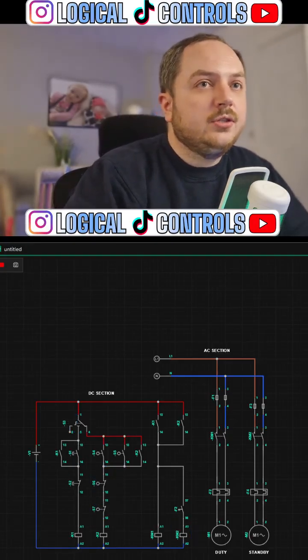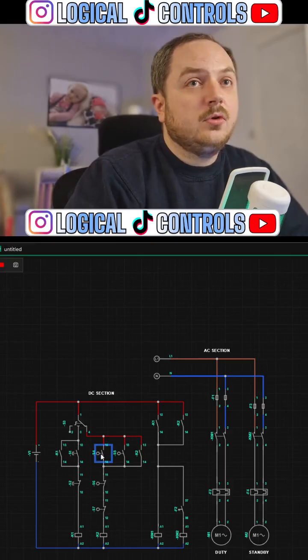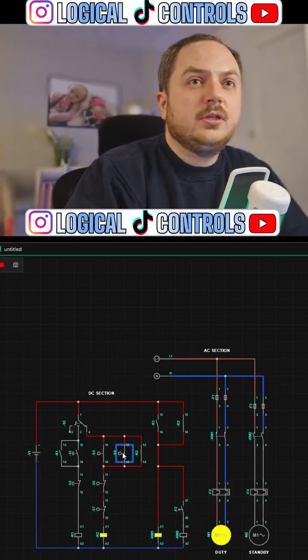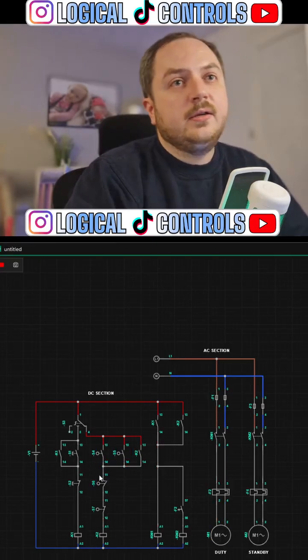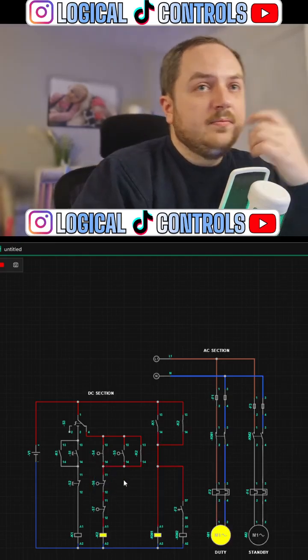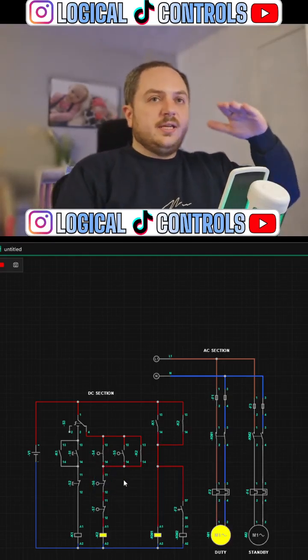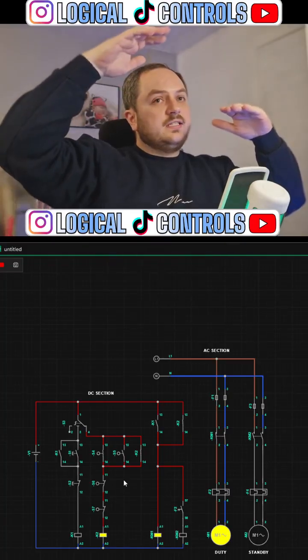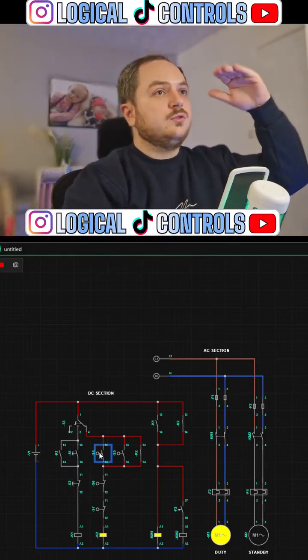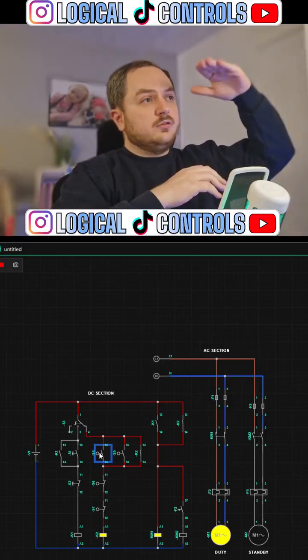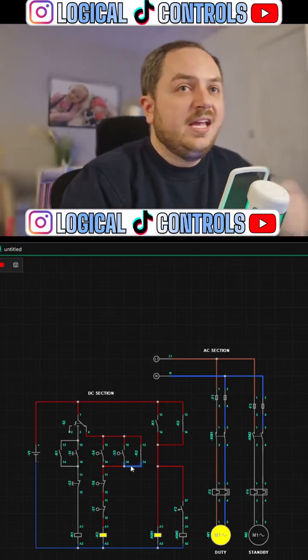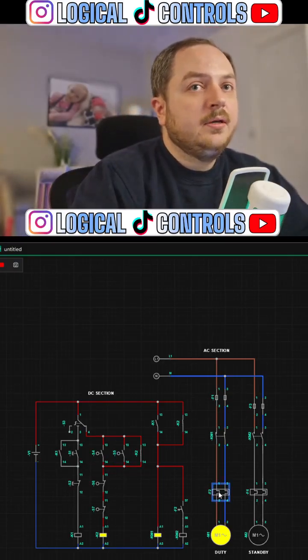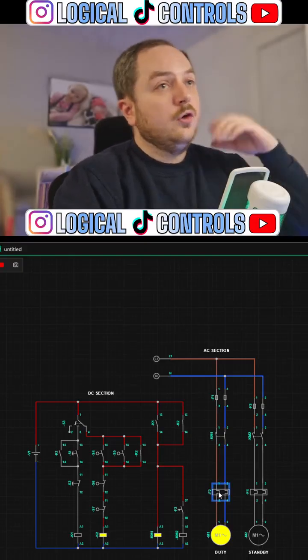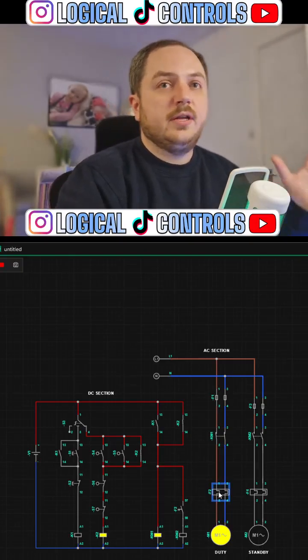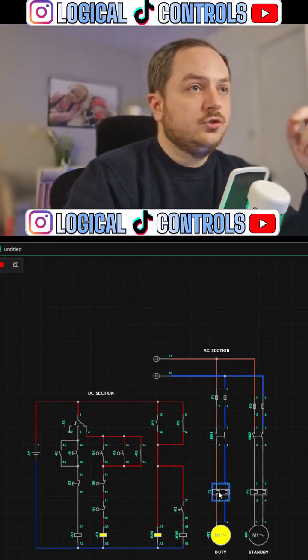We'll go into automatic. We'll close up our 2 lows again. Did we do that? No, we didn't. Never mind. If I want to start it, the low level switch has to be activated. The pump starts running, starts filling the tank. The low level switch would then undo because the liquid level is rising again. If at some point in time that pump overloaded, it couldn't run anymore, the overload would trigger.